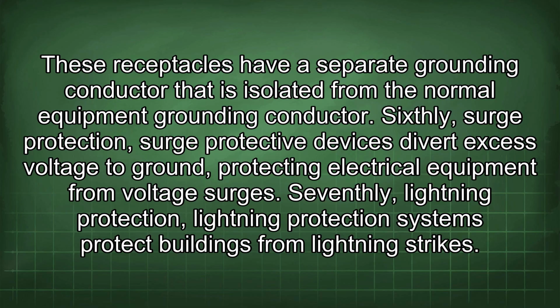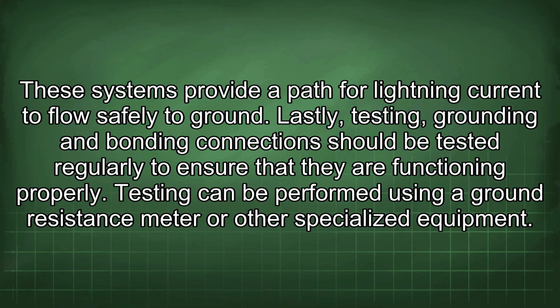Sixthly, surge protection. Surge protective devices divert excess voltage to ground, protecting electrical equipment from voltage surges. Seventhly, lightning protection. Lightning protection systems protect buildings from lightning strikes. These systems provide a path for lightning current to flow safely to ground. Lastly, testing. Grounding and bonding connections should be tested regularly to ensure that they are functioning properly. Testing can be performed using a ground resistance meter or other specialized equipment.